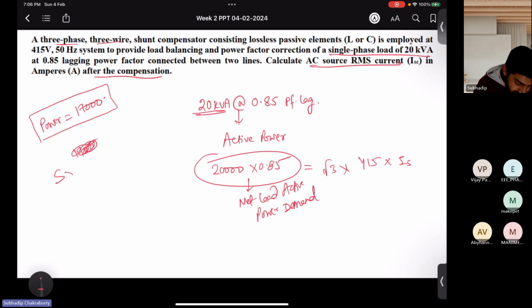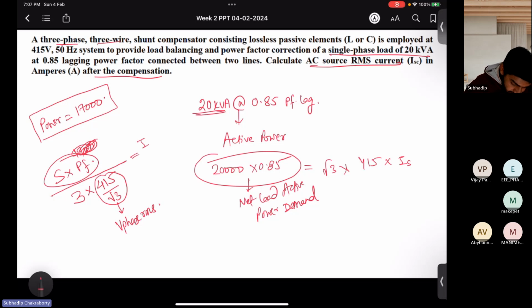So write like this: S into power factor to find out the net active power. Now this power is divided among the three phases equally, and you find out the phase voltage to find out the current. So this is phase V phase RMS. So you should find out the same answer. Just check. 17,000 by 3. Divide 415 by √3. Around 23.65 it is coming, right?